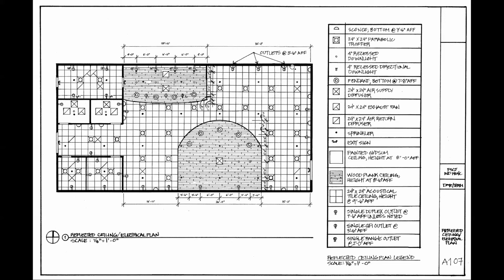So the otherwise noted part happens here. So these outlets are located at 3'6" AFF. And that's so that people who are sitting at the booth can plug in things, because the booth would be blocking the outlets if they were at 1'6" AFF. So that's why they're noted on here.